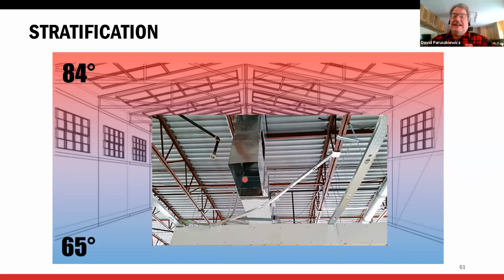What happens if I've got 80, 82 degree air going into this return air here? Because I've stratified, we're going to trip the limit. So even though you don't have a temperature rise higher than you're allowed, if I've got a return air of 78, 80 degrees or higher, you're going to trip the limit, okay?